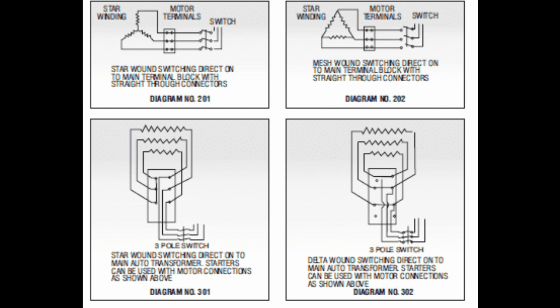In 301 and 302, you can modify the terminal connections as per your requirement. The manufacturer brings all 6 terminal connections to the terminal box. In 301, the windings are bound in star fashion in terminal box. In 302, the windings are bound in delta fashion in terminal box. Here, you can use all types of starters.